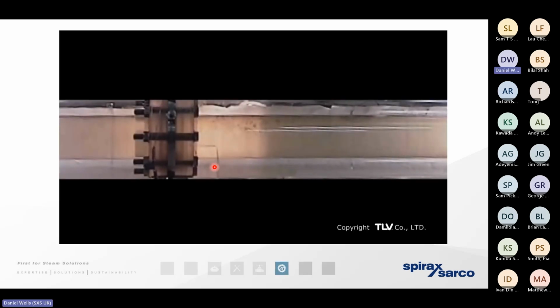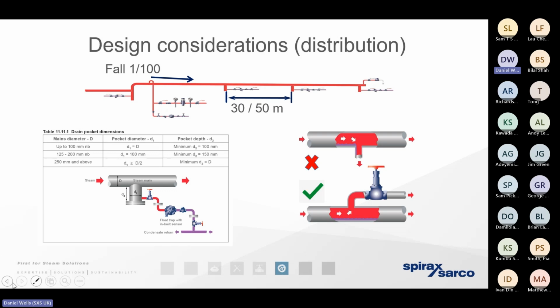The image I'm showing at the moment is actually steam hammer. This is a condensate flooded pipe. You can see that the steam that is introduced into the pipe wants to move at a much, much faster velocity than the condensate does. Then, as the steam moves from one side of the screen to the other, that steam condenses as it gives up its energy. As that steam condenses and collapses, it pulls a vacuum. So the same thing happens all over again. It reminds us how vitally important it is to get that condensate away and separate the steam and the condensate.